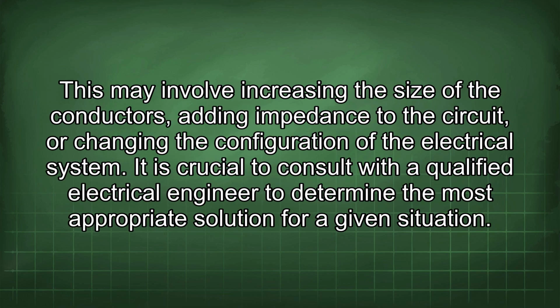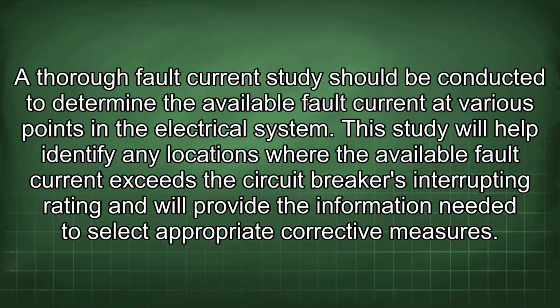Thirdly, modifying the electrical system to reduce the available fault current can also be an effective solution. This may involve increasing the size of the conductors, adding impedance to the circuit, or changing the configuration of the electrical system. It is crucial to consult with a qualified electrical engineer to determine the most appropriate solution for a given situation. A thorough fault current study should be conducted to determine the available fault current at various points in the electrical system. This study will help identify any locations where the available fault current exceeds the circuit breaker's interrupting rating and will provide the information needed to select appropriate corrective measures.